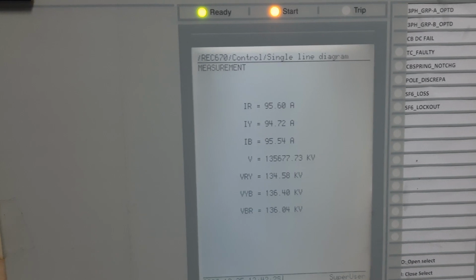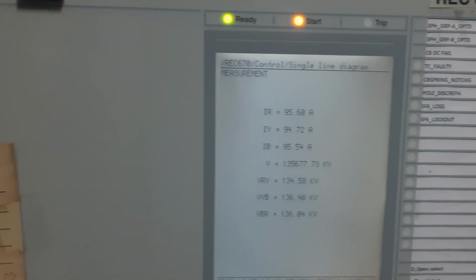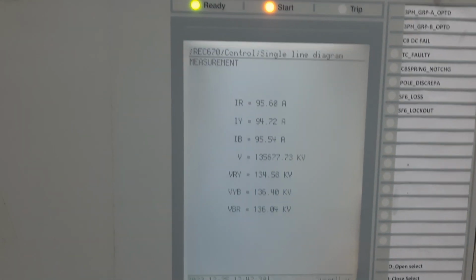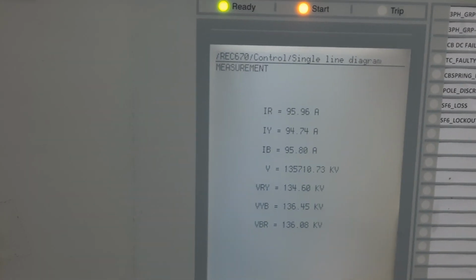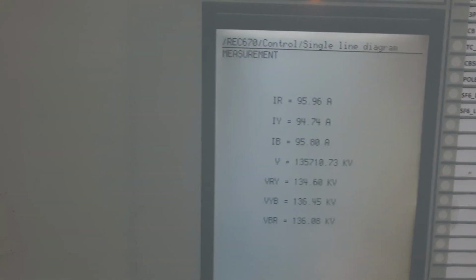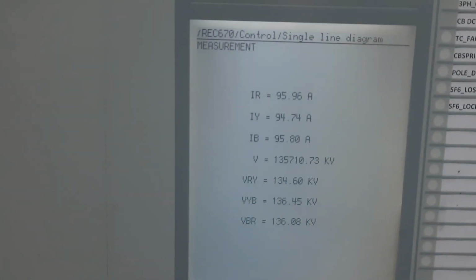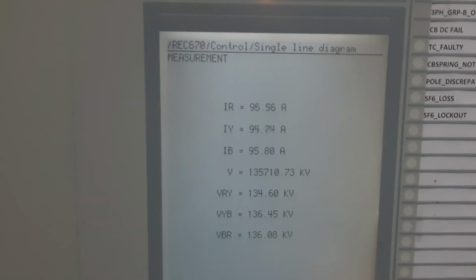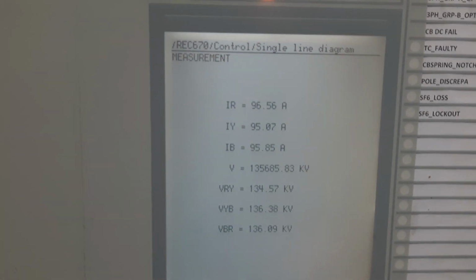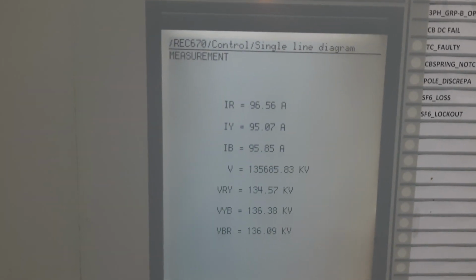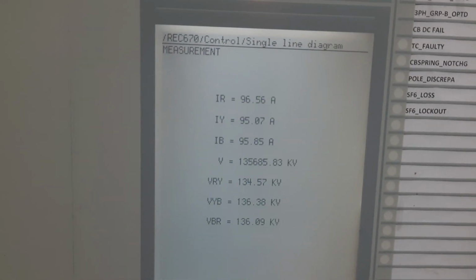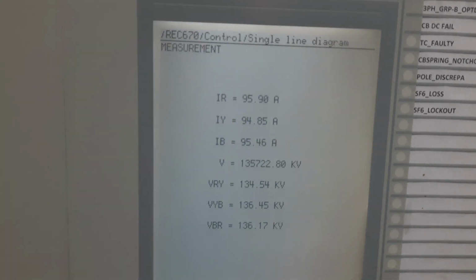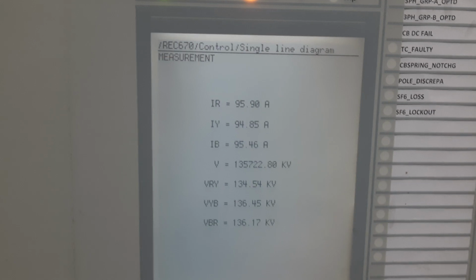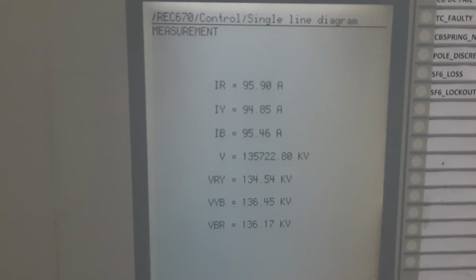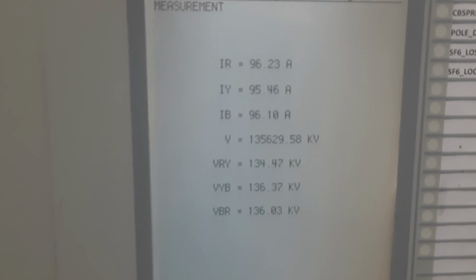And since I'm already here in this BCU, let us calculate our power also, how much power should be flowing in this particular feeder, because we have got the voltage and the current. The voltage is your bus voltage only, see it's 134, and 95, 94, like that, these are the line currents. So knowing these parameters, we'll just take one. Your power will approximately be according to the formula of root 3 into line voltage or your bus voltage into your line current, which are the currents shown here. So let me just calculate. Let me take line current as 95, and I'll take 134 as the bus voltage. So let us just do the calculation.